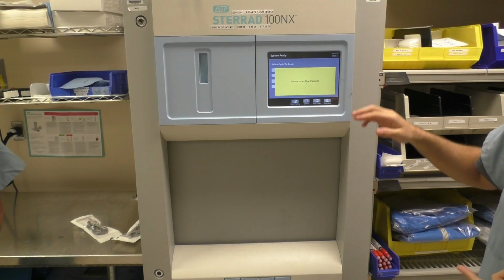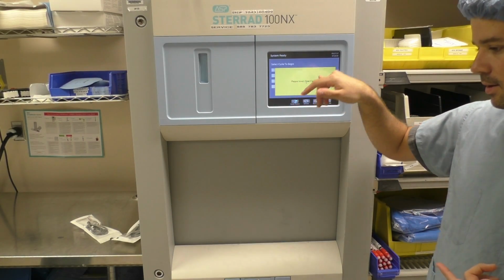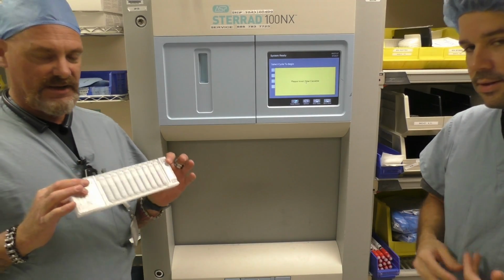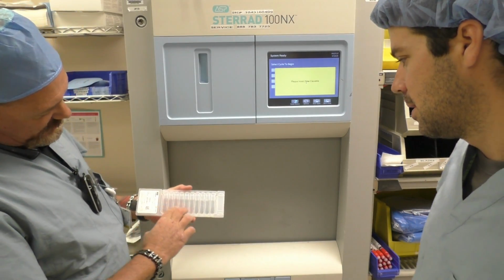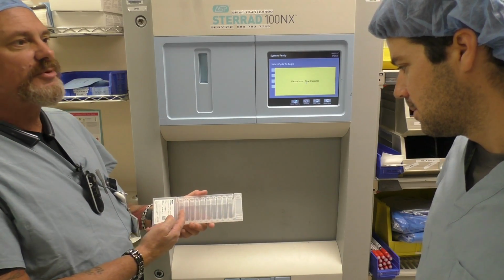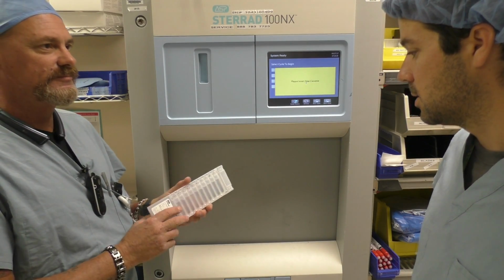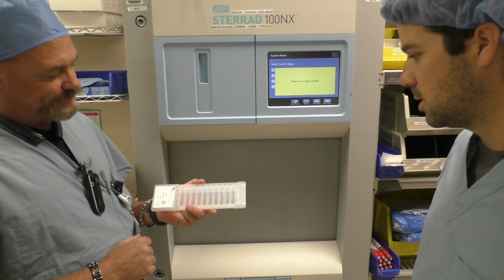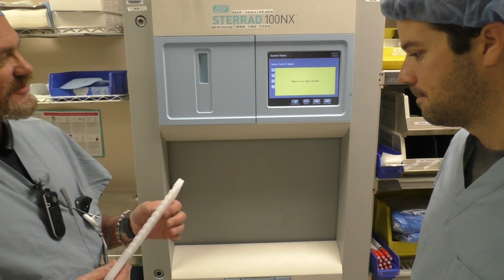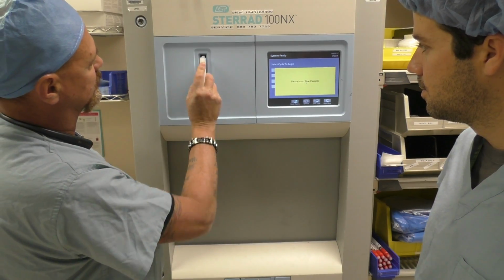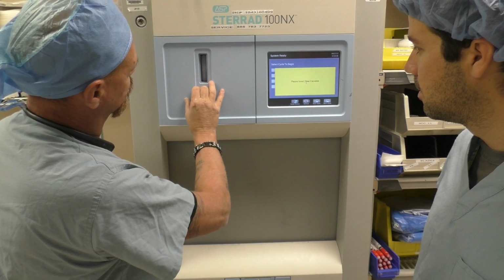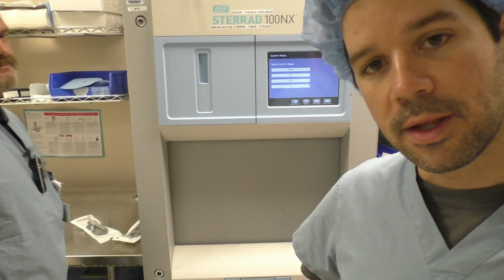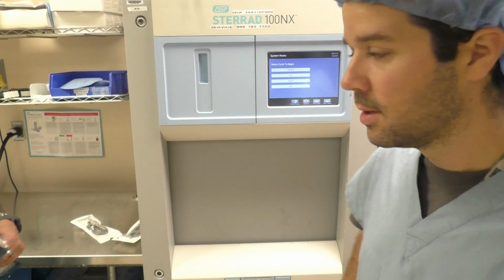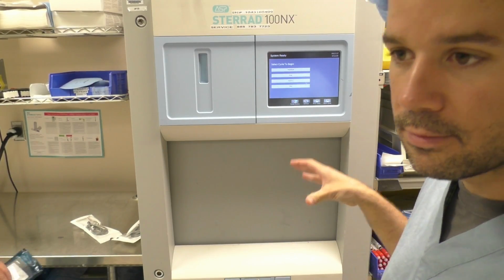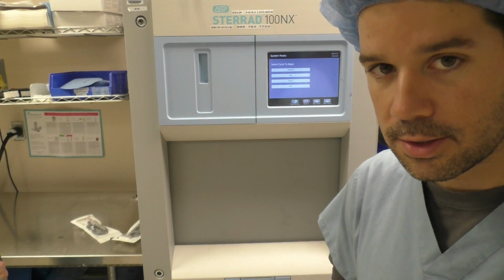So we just turn this screen on and it says please insert new cassette. What exactly is the cassette? This cassette has, you can see all the different vials. This is all hydrogen peroxide. That's what these machines run on. That's what they all run on. That's their sterilization, hydrogen peroxide. So this is the cassette when it says add a cassette. A few moments later. So whereas the big autoclave is steam sterilization at a really high temperature, the Sterrad is a much lower temperature for delicate items using hydrogen peroxide.